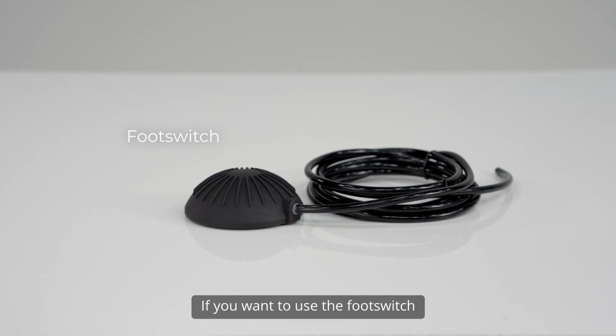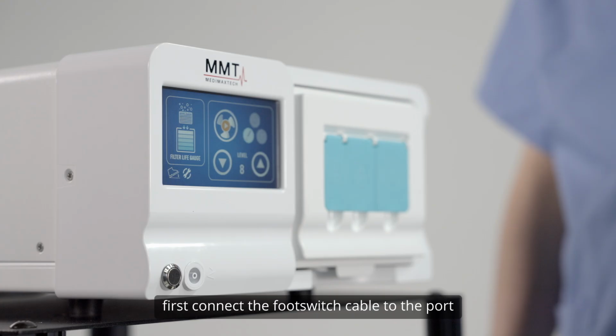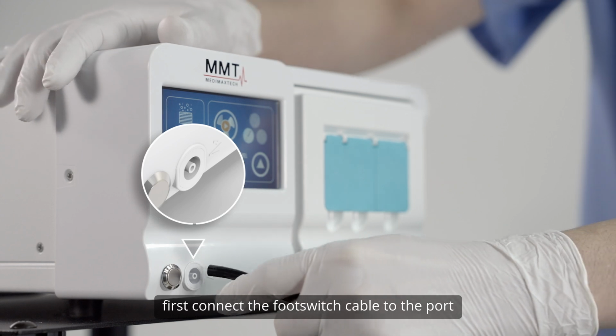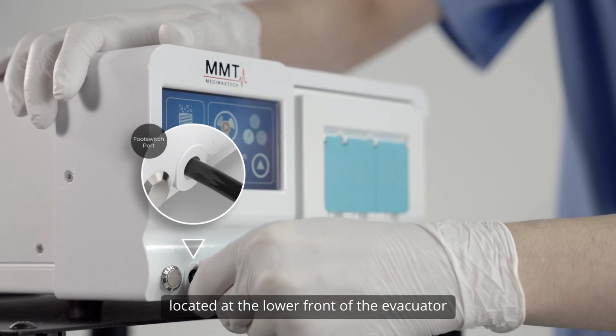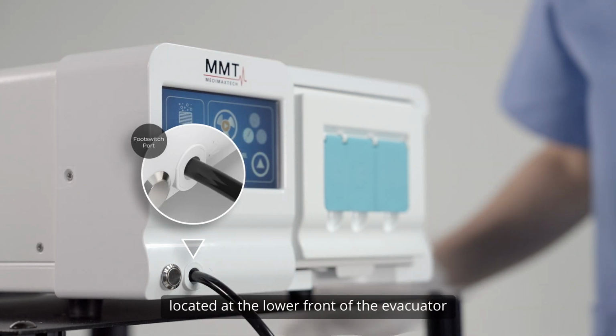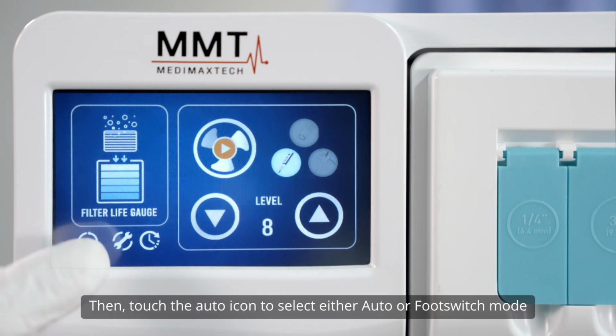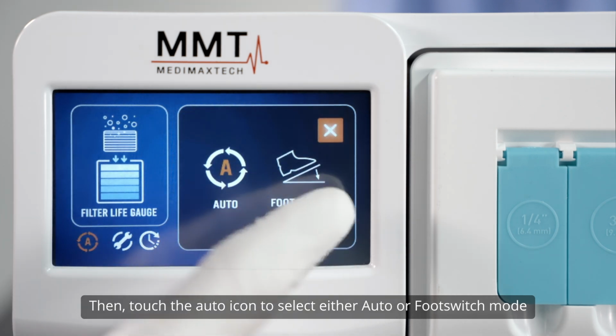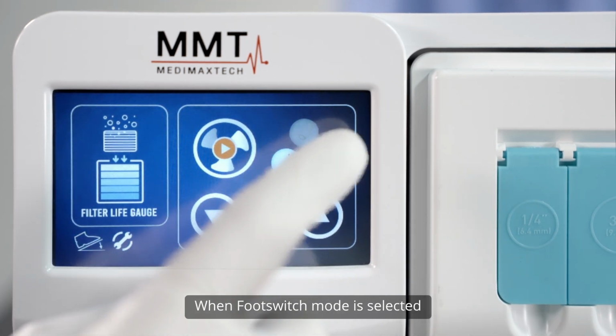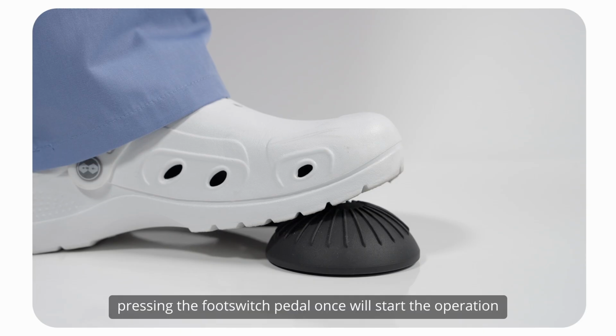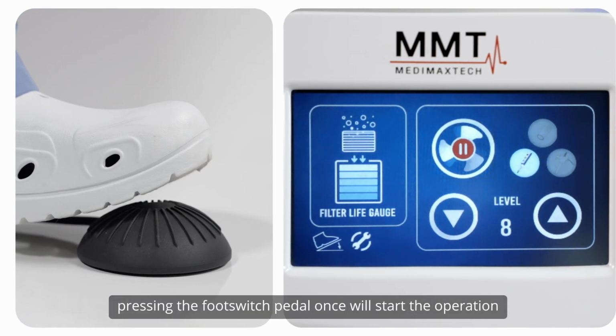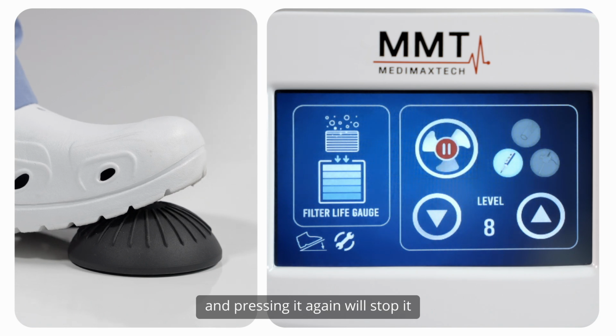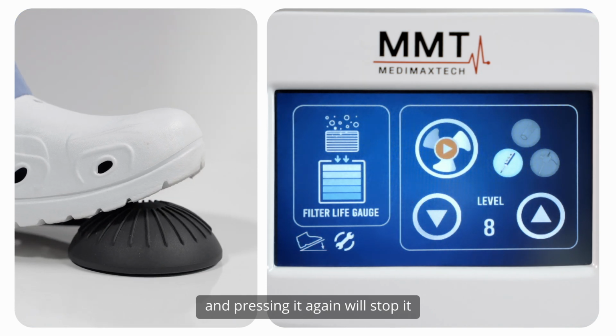If you want to use the foot switch, first connect the foot switch cable to the port located at the lower front of the evacuator. Then, touch the auto icon to select either auto or foot switch mode. When foot switch mode is selected, pressing the foot switch pedal once will start the operation, and pressing it again will stop it.